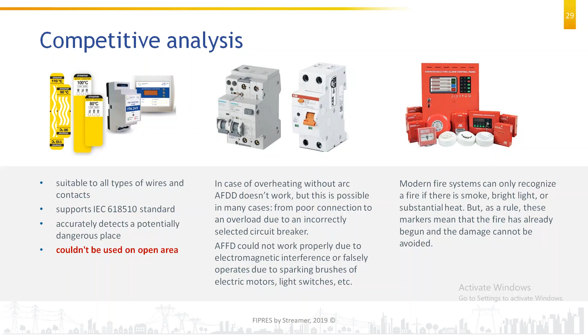FIPRES is suitable for all types of wires and contacts. It can communicate remotely, and it protects potentially dangerous places. So this is a comparison with the arc fault detection device. AFDD and FIPRES are two different applications. The arc fault detection device is for arc flashes, not for slow overheating, and FIPRES is for overheating, not for arc flash. In an arc flash, everything will get damaged, and arc flash detection requires a very fast response, which is designed into the AFDD, not into FIPRES.